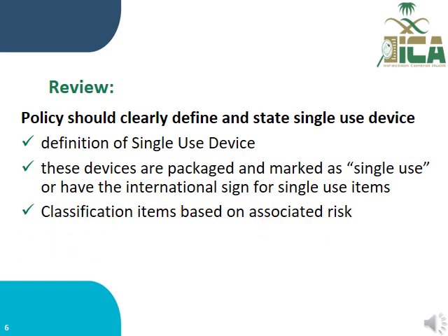You need to review the policy and procedure for the single-use device. This policy should be clearly defined and state the single-use devices, and it should include the definition of a single-use device as we mentioned before, and also how we know whether a device is single use or not. It should mention that these devices are packaged and marked as single use, or they have the international sign for single-use items. And also the classification of these items based on associated risk, like critical, semi-critical, and non-critical items.